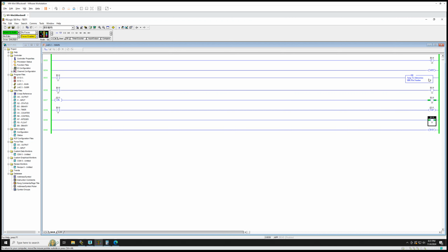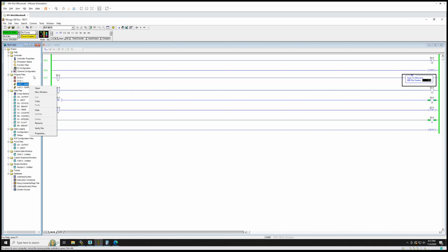You would need a jump subroutine if you have more than one ladder. So typically what would happen is you would have a main, and everything in the main would be like your flasher timers, and you can have an always on, always off bit. And then you would have jump to subroutine for all the other routines of your job because the program set up to this to be the main. The rest of them need to be added or jump to the subroutine and get called. So that's typical, and at that point you don't need a return on the subroutine.